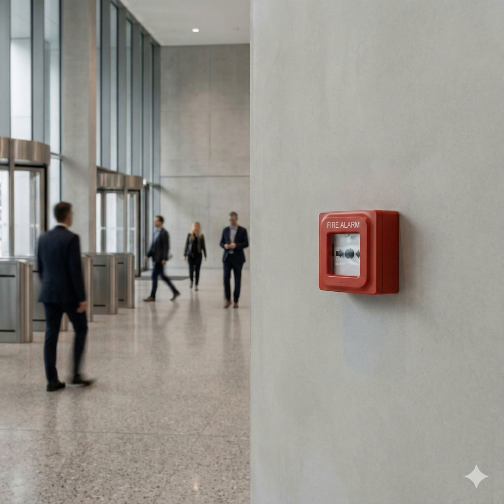And this interface brings us to the operational control layer, the firefighter's smoke control station, or FSCS. This gives them manual override. The FSCS is a key life safety device. While the fire alarm system automatically initiates smoke control sequences, activating fans, closing dampers, firefighters, once on scene, must have the ability to manually override those sequences. The FSCS panels show the real-time status and allow them to take manual control of the HVAC systems to assist with tactical operations, like directing airflow to contain smoke.